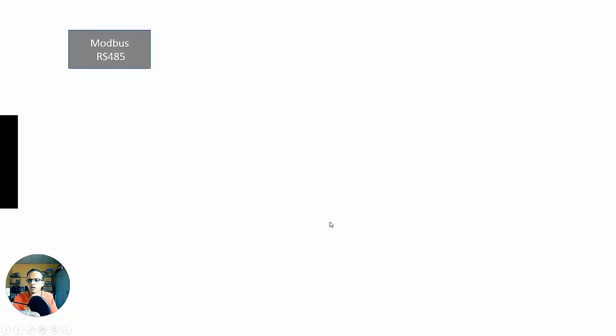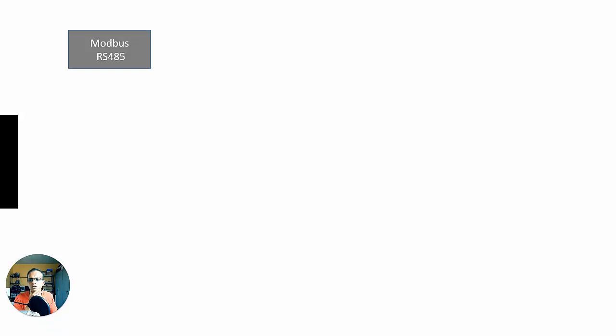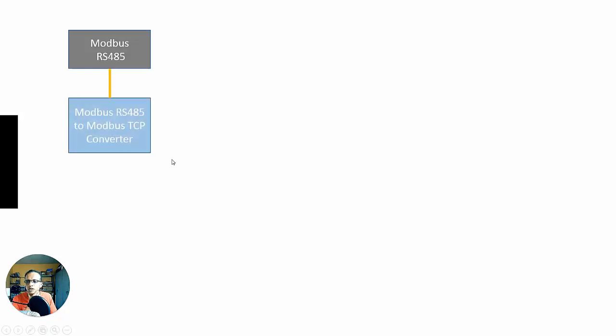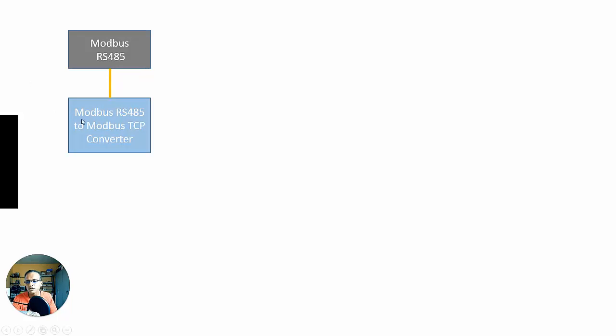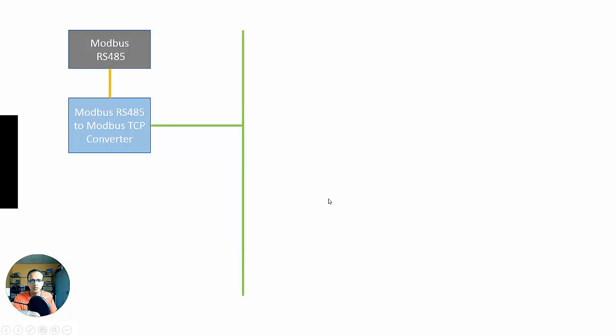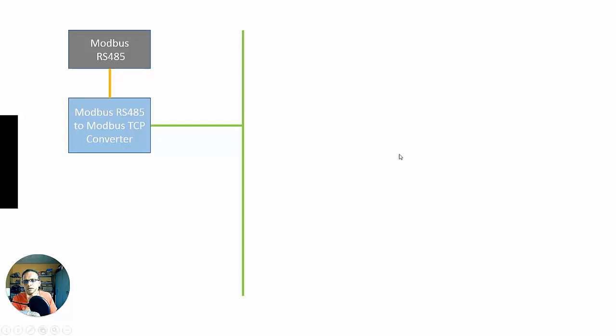So I just want to use an example scenario to look at the before and after. So let's look at classic OPC, an example scenario. Let's say I have a Modbus RS-485 device, and I'm in charge of integrating that into the plant network. Well, the first thing I would do is get a converter, a Modbus 485 to Modbus TCP converter, connect the 485 side to there, and then connect my converter to the plant network. I want to get rid of all this serial device stuff by converting it all to TCP.